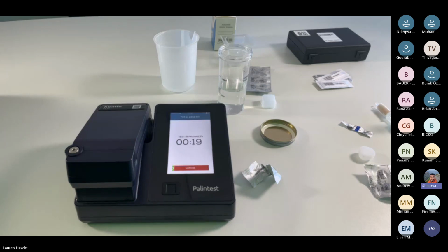So we have 20 seconds left and we'll get a total arsenic result. So again, just those things in there. Everything you can see on the screen is supplied with the kit. You don't need to purchase anything extra. You will get everything there. Take a sample of the water, follow the on-screen instructions. All of that technical ability happens in the background, and in 1 second, you will get a result on screen. Now that's good because we just have taken tap water samples, so we have got less than 2 micrograms per litre. The test range on this device for arsenic is 2 to 250 micrograms per litre.